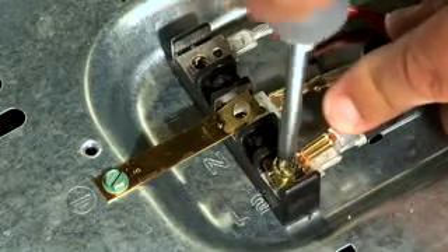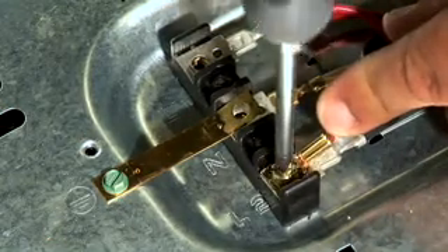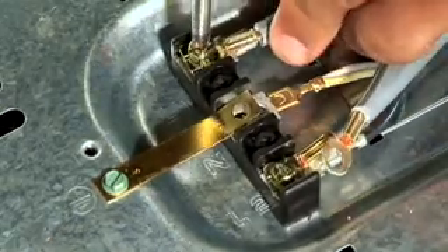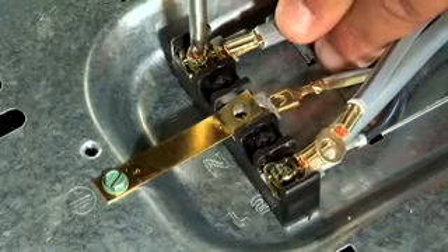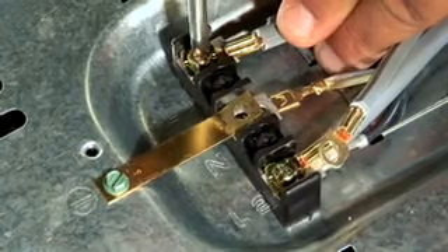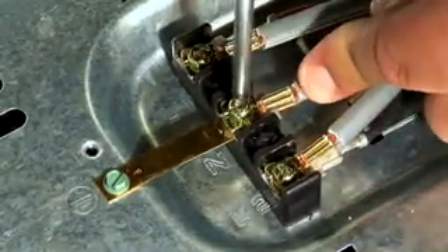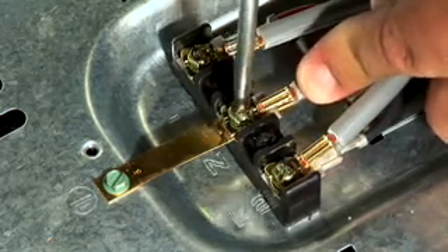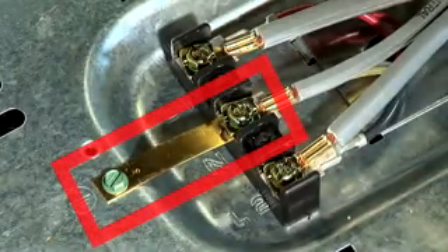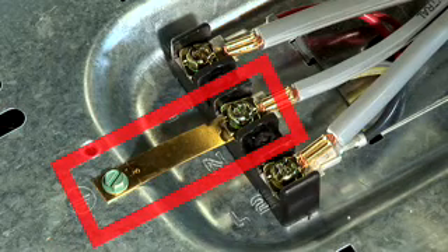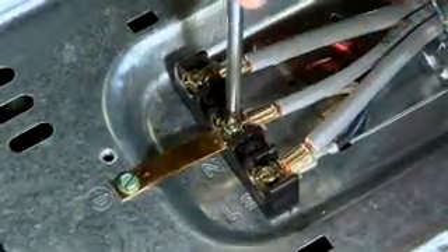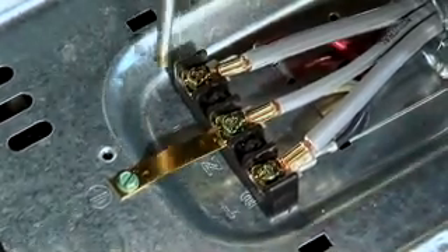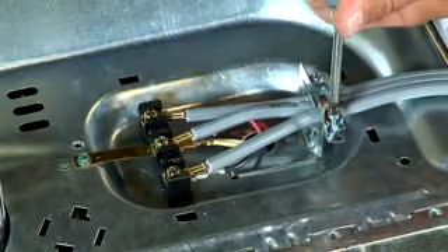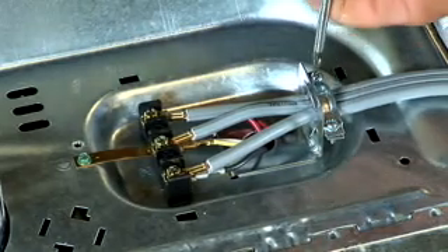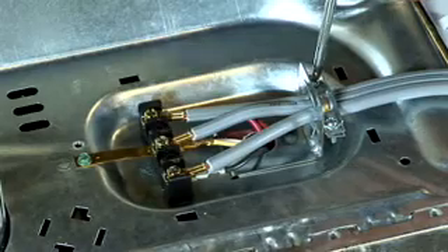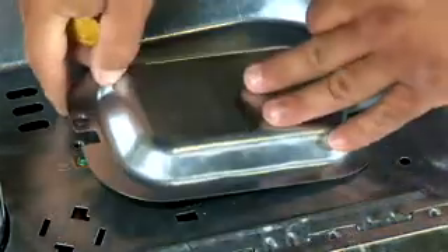Connect the power cord as follows. Connect the 2 hot lines to the outer screws of the terminal block. Then connect the neutral line to the center of the terminal block. Be sure the ground strap is connected to the neutral terminal of the block and to the green ground screw on the cabinet rear. Tighten all of the terminal block screws completely. Properly secure the power cord to the strain relief. And finally, reinstall the cover.